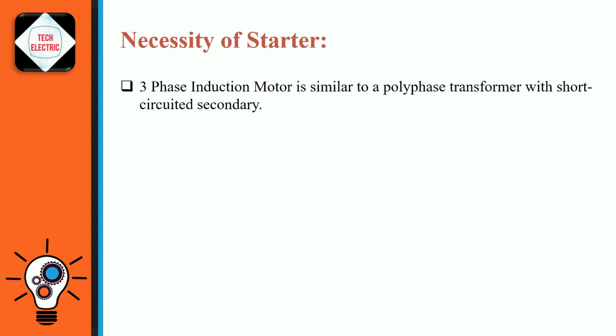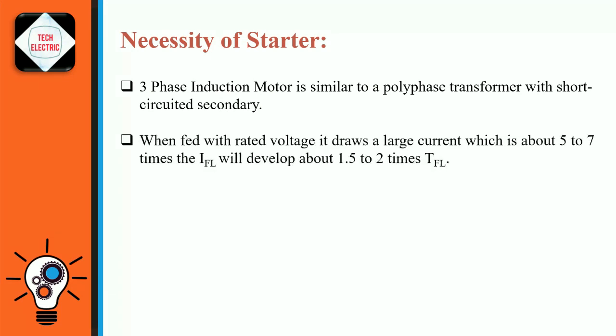Before starting with the construction and working of Auto Transformer Starter, let's quickly understand its necessity. Three-phase induction motor is similar in action to a polyphase transformer with short-circuited secondary. Therefore, when a rated voltage is applied to the stationary motor, it will draw a large current which is about 5 to 7 times the full-load current and will develop about 1.5 to 2 times full-load torque.